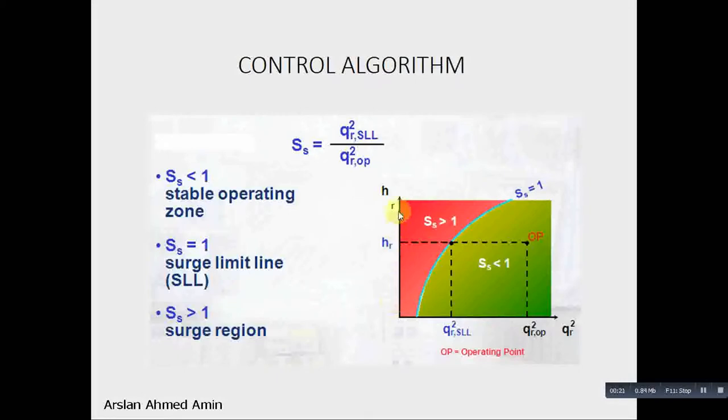So this is how the surge map would be built in the controller. This is the reduced polytropic height and this is the reduced flow. And this is your surge limit line. This is the red region below this line, and above this line, the upper side, which is the green region, is our safe region.